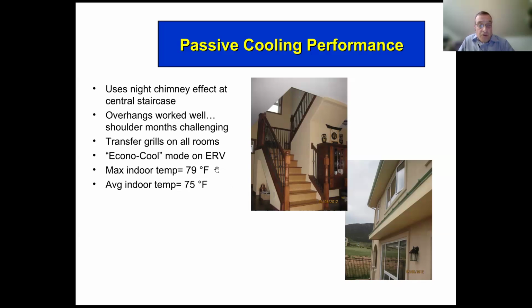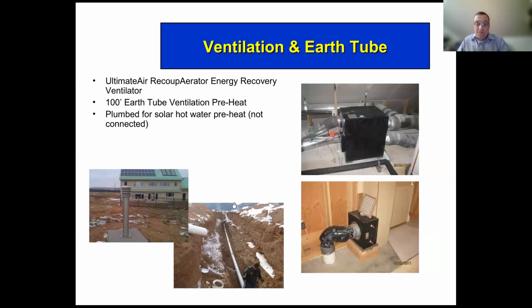Our energy recovery ventilator also has an Econo cool mode, which turns off the heat transfer function. And so if we have to use the mechanical ventilator in the summer, that also provides some cooling. And as we mentioned earlier, the overhangs work well, but the shoulder months are probably more challenging than other months. The ventilation system is an energy recovery ventilator, which transfers between 80 and 82% of the heat energy in the stale outgoing exhaust air to the incoming fresh air.